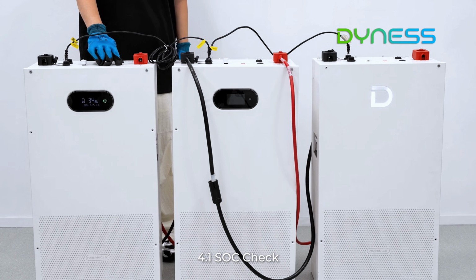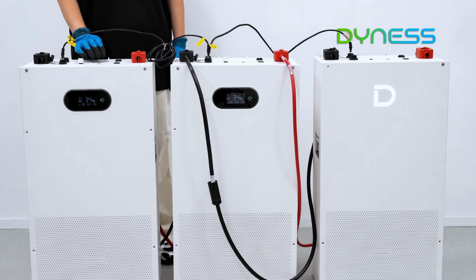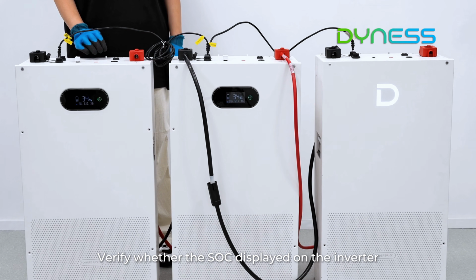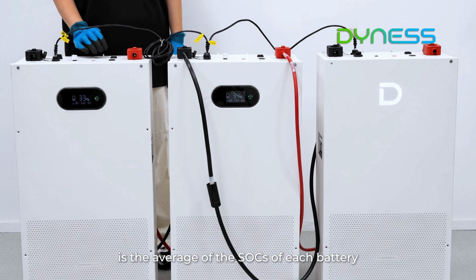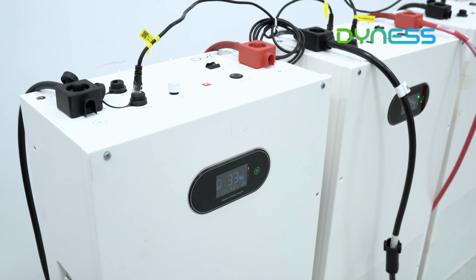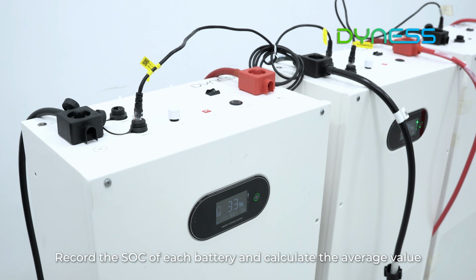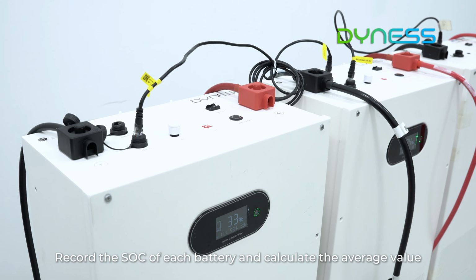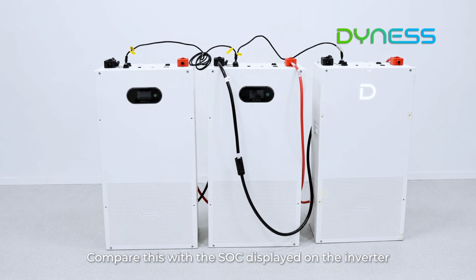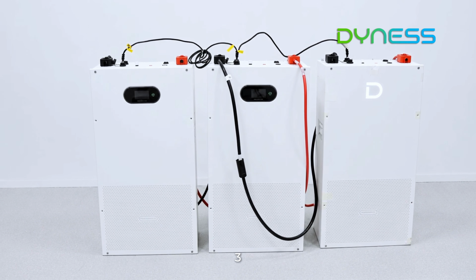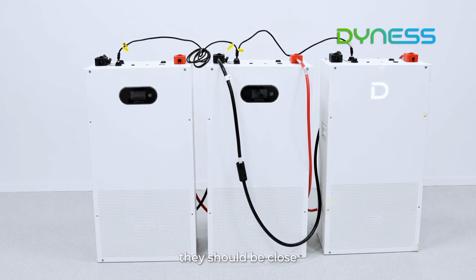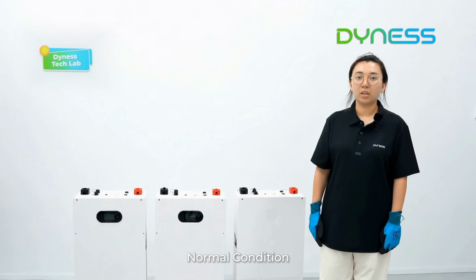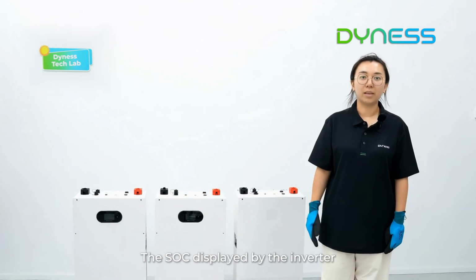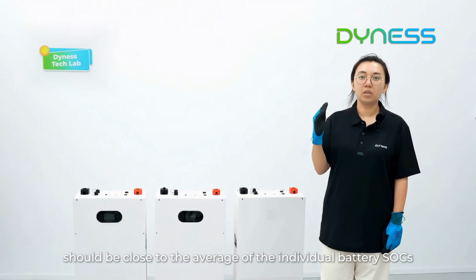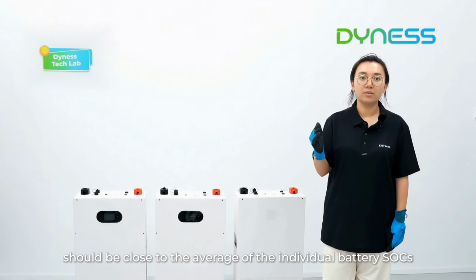4.1 SOC check. Test objective. Verify whether the SOC displayed on the inverter is the average of the SOCs of each battery. 1. Record the SOC of each battery and calculate the average value. 2. Compare this with the SOC displayed on the inverter. 3. Under normal conditions, they should be close. Normal condition. The SOC displayed by the inverter should be close to the average of the individual battery SOCs.